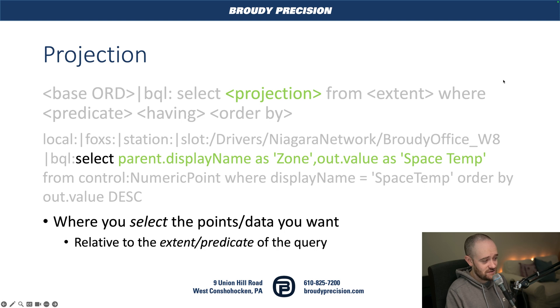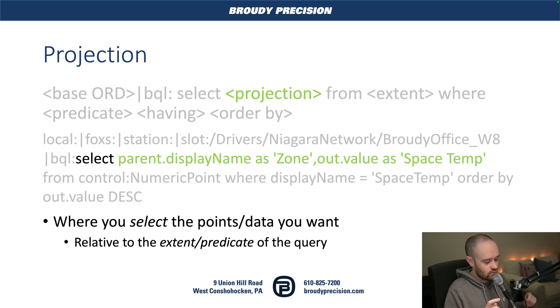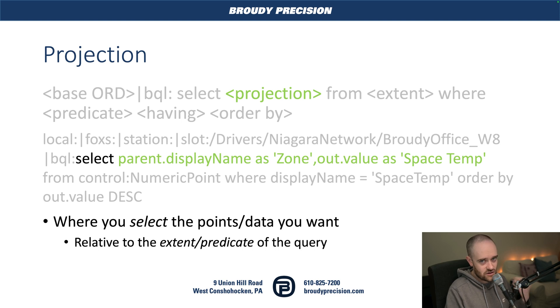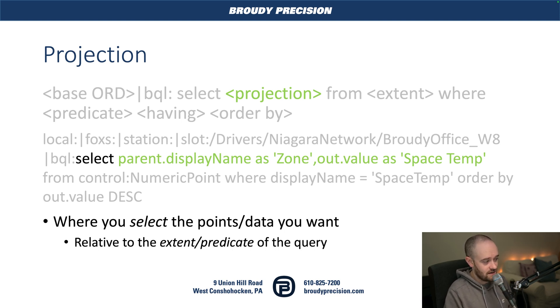Next is our projection. This is where we're selecting what we want to have in our columns of the query or the return of the query. In this case, I'm looking for the zone, which is the parent dot display name of the space temps that I've found, and then I'm also going to output the out dot value of our space temp and call that space temp. The syntax here allows us to define a custom name — the "as zone" and "as space temp" are what define our column names on the returned results of the query.